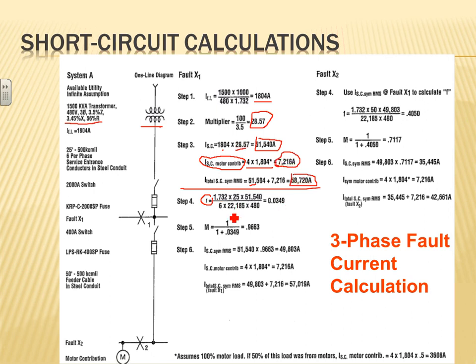The most important thing is the contribution component. I don't know if you can see, I have 25 feet here of 6 runs of steel service entrance of 500. So I have 25 feet of 500 kcm, 6 per phase.